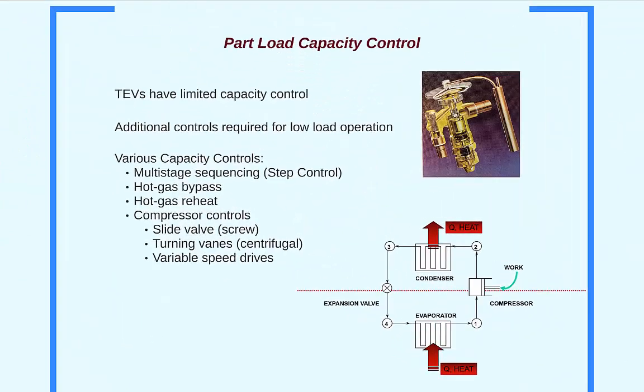The last topic we will discuss in this lesson is various controls available to handle part load operation. Most residential DX units are two-position control. They are either on or off. The expansion valve regulates the flow of refrigerant to meet the cooling load as we just discussed. But the expansion valve is limited in how much it can modulate the unit's cooling capacity. For instance, let's say you have a 10-ton DX unit, but only need half a ton of cooling during one of the shoulder seasons. A thermal expansion valve is not designed to modulate flow to 5% part load capacity. Other staging controls are necessary.